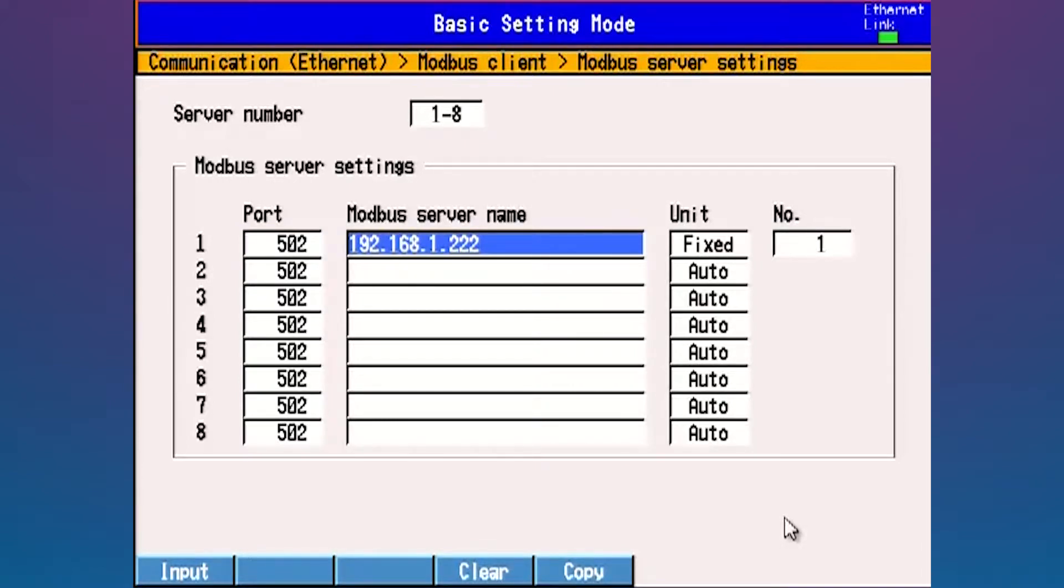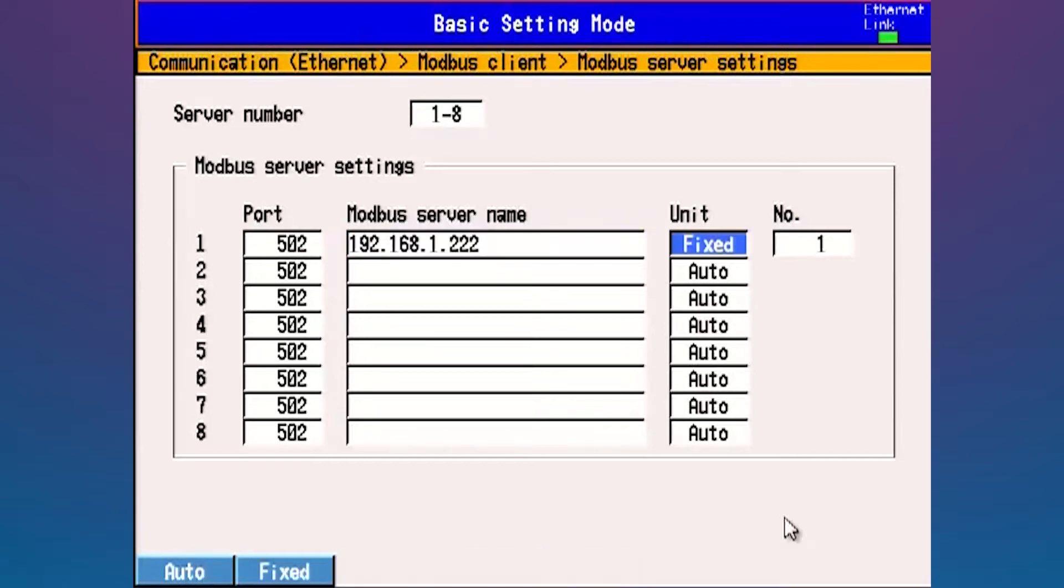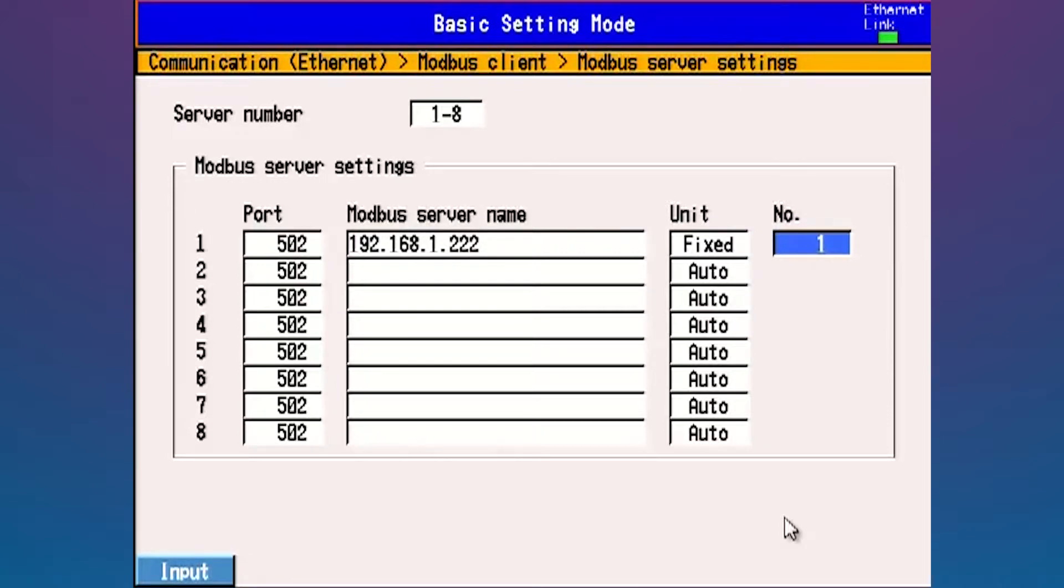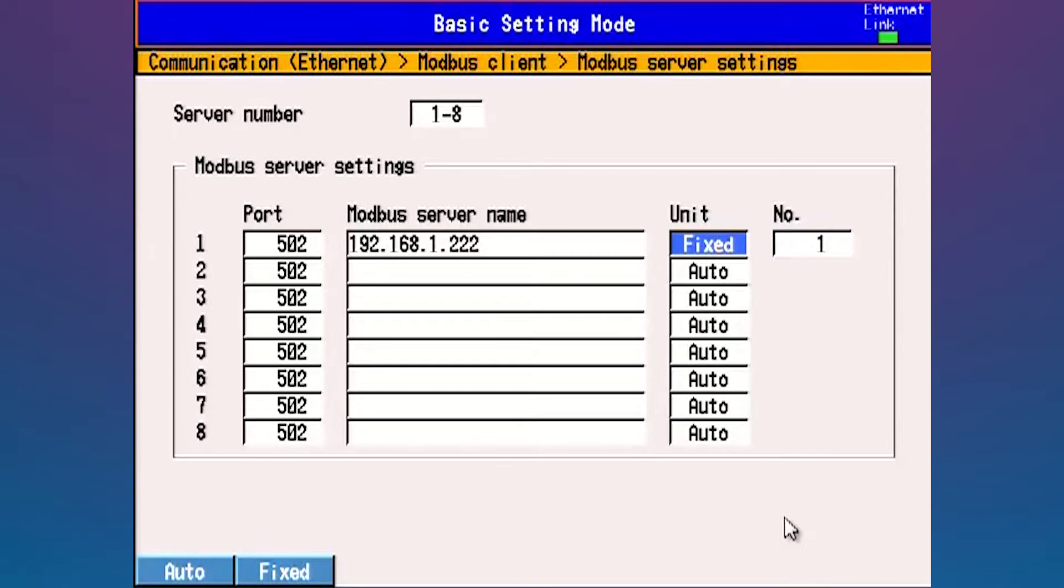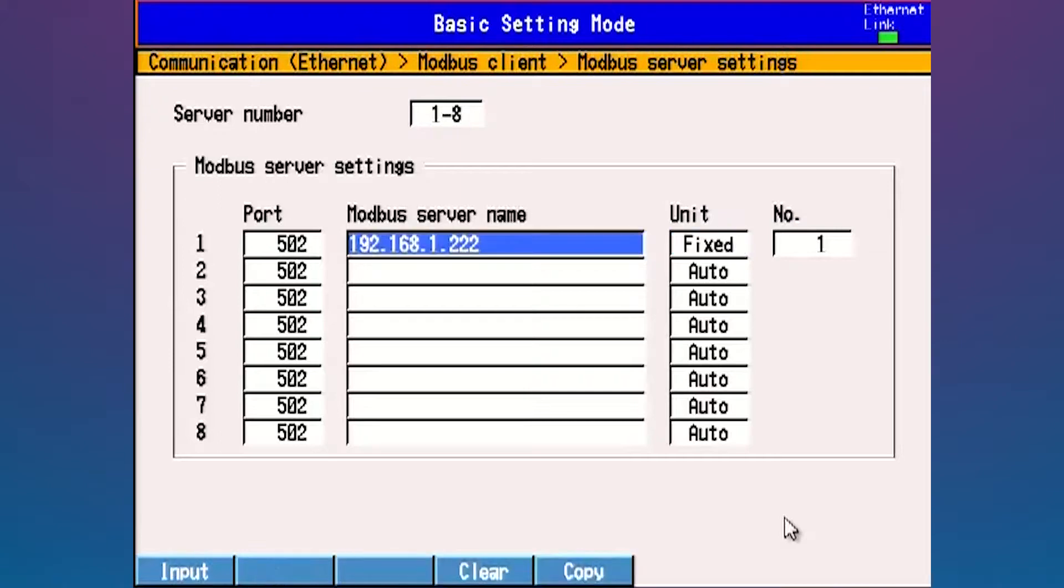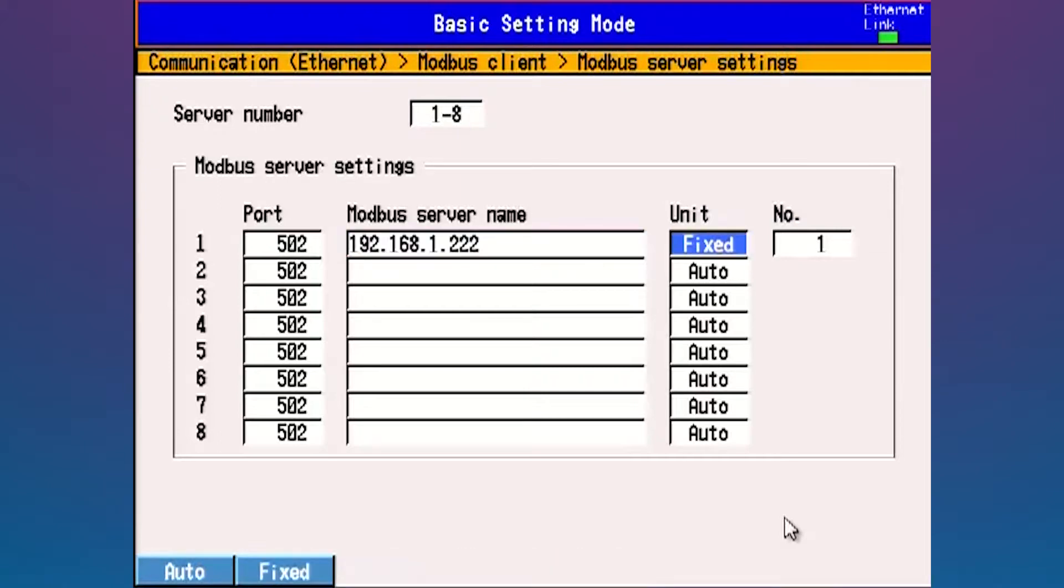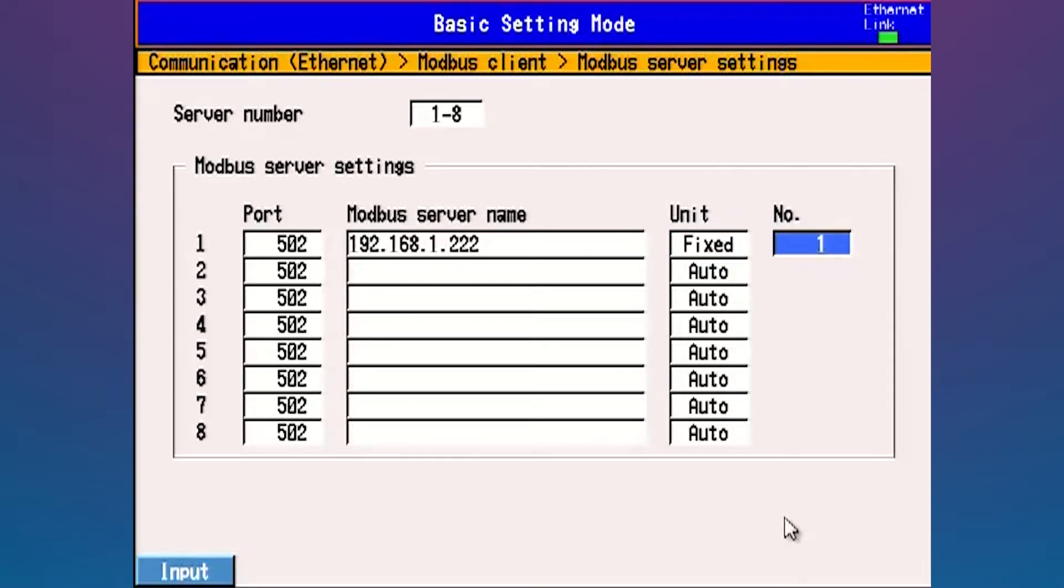This is the IP address of the MW100 or DAC master. This is the IP address of whatever remote device you're hoping to communicate via Modbus. The unit number is generally going to be fixed and one. I rarely leave it on auto. This is a throwback to the old serial communications of Modbus and it allows you to access subunits that may be off the same IP address. But in this case, there are no subunits, so we can just go with fixed and number one. Hit display enter to accept my choices and escape to back out.